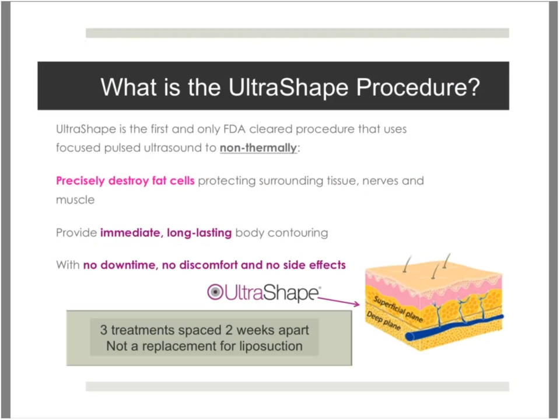So really, it's a quick in-and-out procedure for your patient. So this is a great schematic. I love it. This is going to show you how the ultrasound gets from the handheld piece to the targeted fat cell. Well, what happens is that you have an alternating electric voltage that's applied to the electrodes in the transducer. This creates an alternating electric field within the ceramics, and the alternating electric field then creates alterations in the thickness of the ceramics, which creates a cone of focused, pulsed, high oscillating pressure waves.